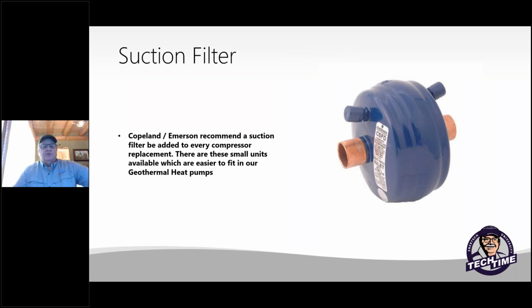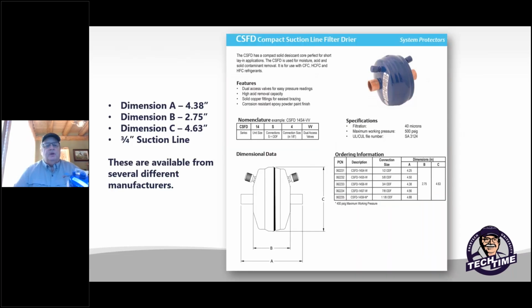One thing that Emerson Copeland recommends is that a suction filter be added to the refrigeration compressor replacement. There's not a lot of room in our units, but this particular suction filter style, as you can see, is very small and compact and has a better probability of fitting inside of a cabinet. I got some dimensions here to show you this particular one. If you look at the far width of it here, it's only under 4.5 inches, so you get a very small space it can fit, and it actually only needs about 3 inches for where the copper tubing pipes will go in.